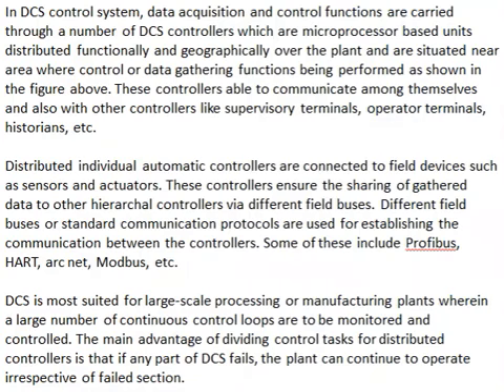Different field buses or standard communication protocols are used for establishing the communication between the controllers. Some of these include Profibus, HART, ArcNet, Modbus, etc. DCS is most suited for large-scale processing or manufacturing plants wherein a large number of continuous control loops are to be monitored and controlled. The main advantage of dividing control tasks among distributed controllers is that if any part of the DCS fails, the plant can continue to operate irrespective of the failed section.